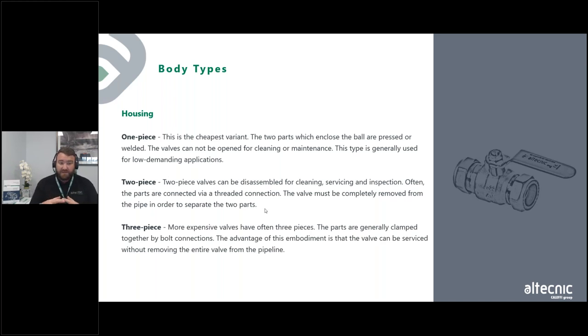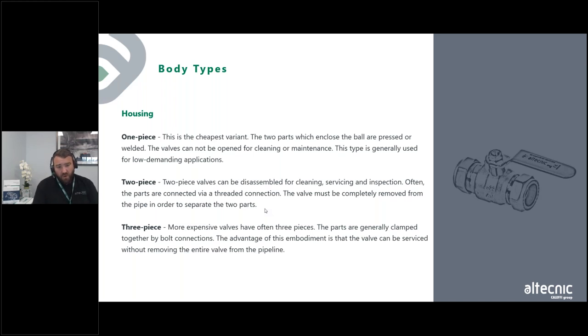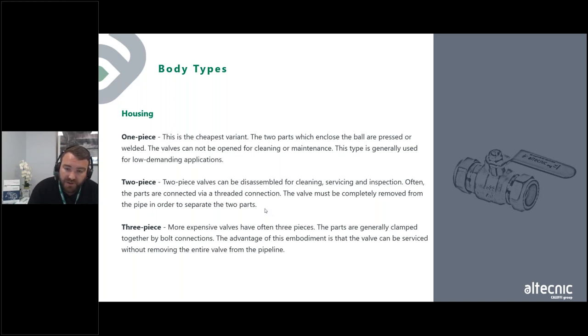The three-piece valve is more expensive. The three parts are generally clamped together by bolt connections, and the advantage is that the valve can be serviced without removing the entire valve from the pipeline. You tend to see these on effluent plants, chemical plants, or petrochemical sites — generally in stainless steel. You'll see four bolts passing through the outer body: one connection side, the center body with the ball, and a third connection side all clamped together. These are more specialized valves, not something you'd see in a domestic property.